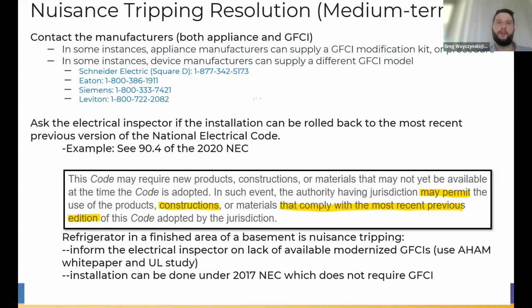Let's say we have a refrigerator in a finished area of a basement that is nuisance tripping. So according to the 2020 NEC, that refrigerator has to be GFCI protected. But what we can do is we can go to the local electrical inspector and we can say, there is a lack of available modernized GFCIs. There are new products that are not yet available. These old GFCIs have not been updated. And you can use an AHAM white paper, which I'm going to make available to UASA. And I'll also give you the PDF of that UL study.